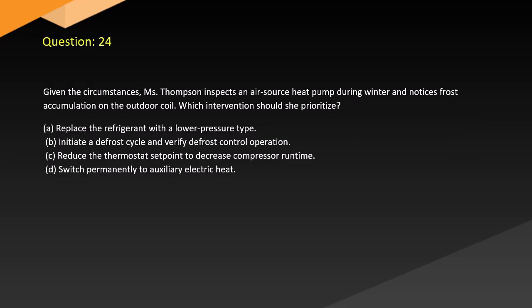Question 24. Given the circumstances, Thompson inspects an air-source heat pump during winter and notices frost accumulation on the outdoor coil. Which intervention should she prioritize? A. Replace the refrigerant with a low-pressure type. B. Initiate a defrost cycle and verify defrost control operation. C. Reduce the thermostat set point to decrease compressor runtime. D. Switch permanently to auxiliary electric heat.